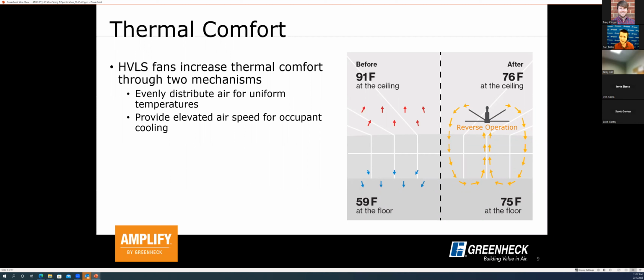The other is that the fans are actually able to provide elevated air speeds for occupant cooling in summer applications, or again, maybe an unconditioned application that has no air conditioning equipment. So basically you can think of this like the fan providing a breeze across somebody's skin. It's not actually cooling the air in the space, but by providing that airflow, that air movement across their body, we're able to make them feel a certain amount of temperature offset or a certain cooling effect based on just evaporation of sweat off of their skin. So it's a very effective way to provide, again, that creature comfort, particularly in unconditioned spaces.